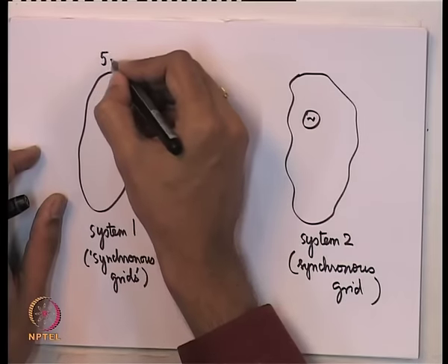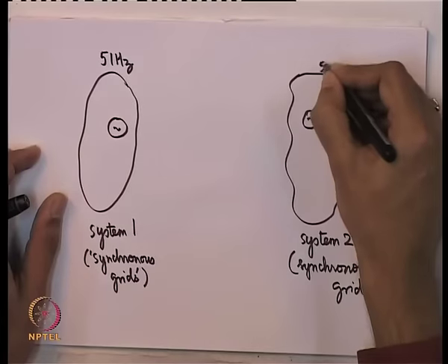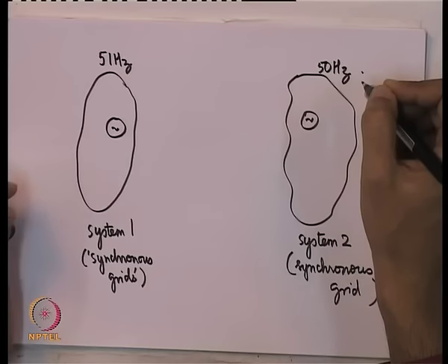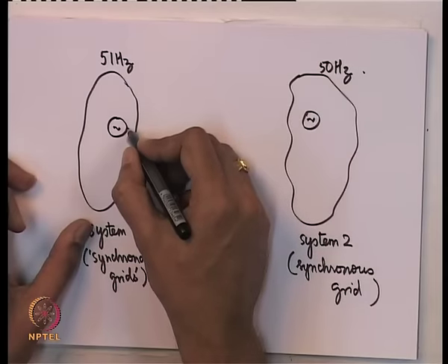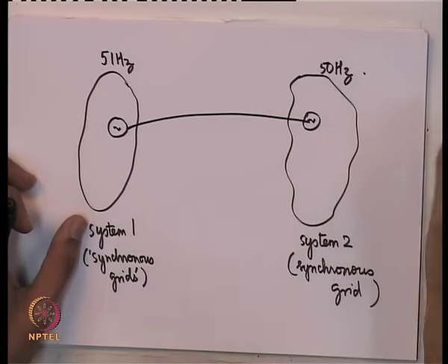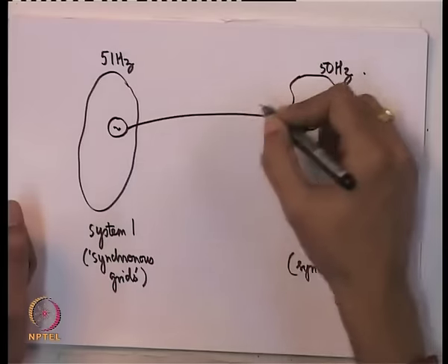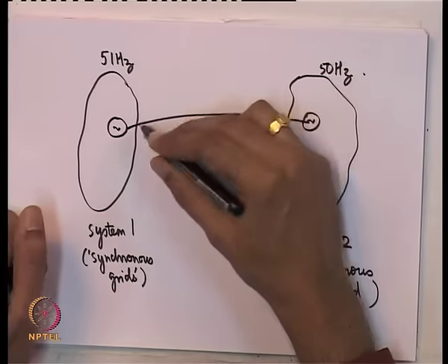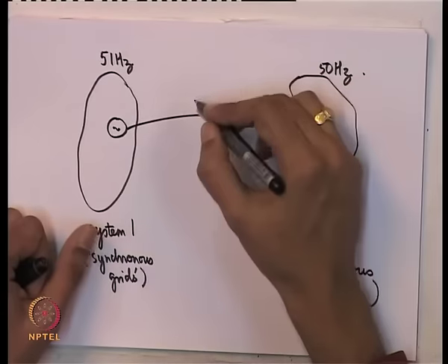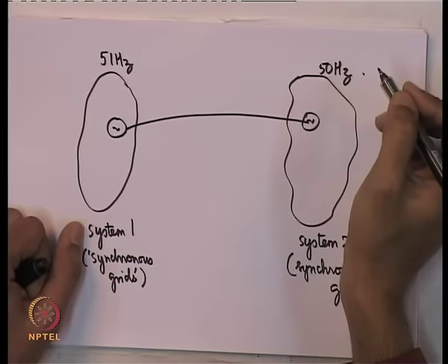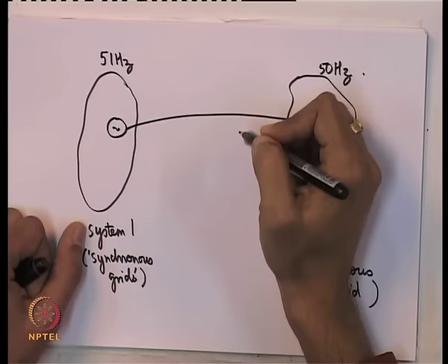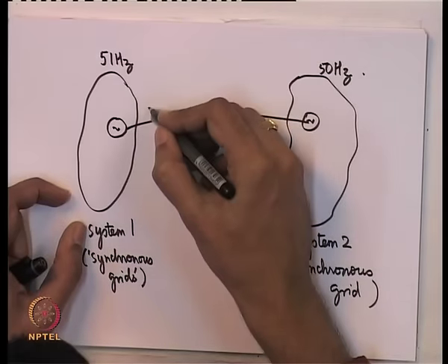They have many synchronous machines interconnected together by AC lines. Suppose this is running at 51 hertz and this is running at 50 hertz. They are happily running at different frequencies, but if I decide to interconnect them by an AC line, there is going to be a problem. I can't just connect them just like that. They may not synchronize. And the second thing is that if they don't synchronize, you are going to have a large number of power and voltage variations.